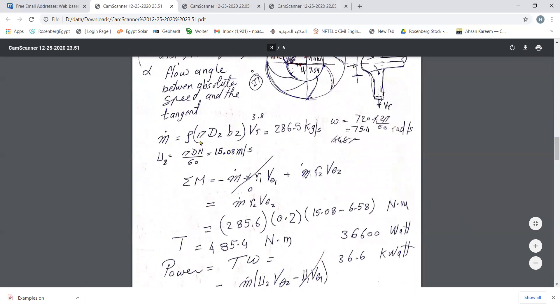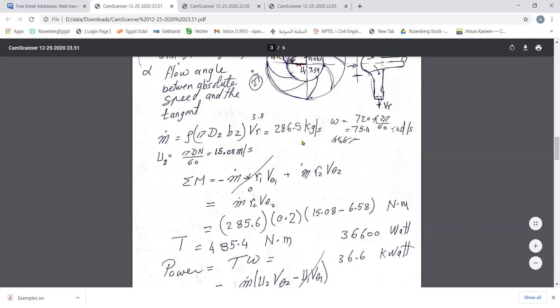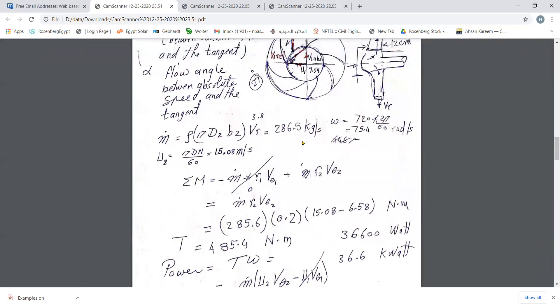The mass flow rate is calculated from the side area π d₂ b₂ multiplied by the radial speed v_r, then multiplied by ρ, giving approximately 286.5 kg/s. The impeller rotates at 720 rpm — like an eight-pole motor. This gives ω = 720 × 2π / 60 = 75.4 radians per second.